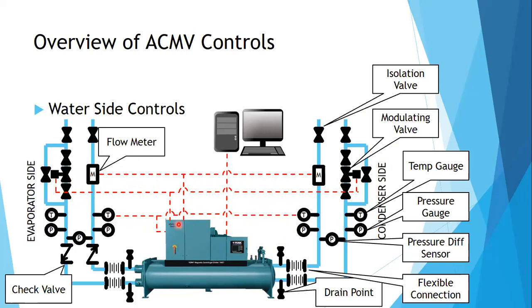Usually, the chillers have their own control logic and control sequence. It's not on the BMS. Your BMS is only to monitor. Okay? This chiller, the engineers don't use logic. It's the manufacturer who makes the logic to ensure the efficiency of the chiller that they are selling. So example, you're buying from York or Trane or Carrier. They have their own proprietary software, they have their own proprietary logic to ensure that their equipment, their chiller, is running on top condition. However, your BMS can extract this data from your chiller units.